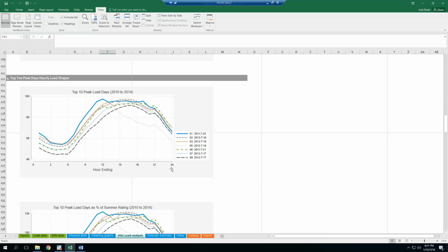But we can see very quickly what the hours of the peak are, the magnitude of it, and what month it happened. So very quickly, I see most of these days happen in July. And this is over a 4-year period. And we see that the peaks are primarily in 11, 13, and 12. So the cool years didn't even hit the top 10. And we also see that, at least for one of those days, it seems to be pretty extreme.